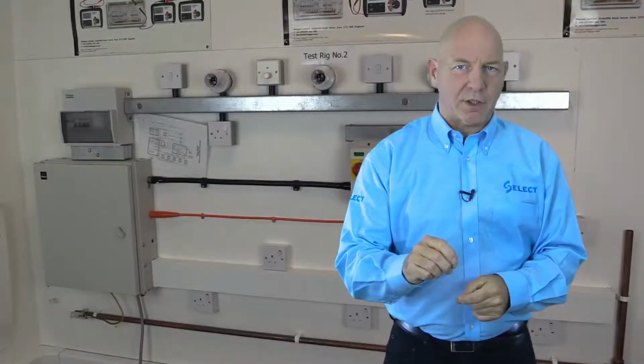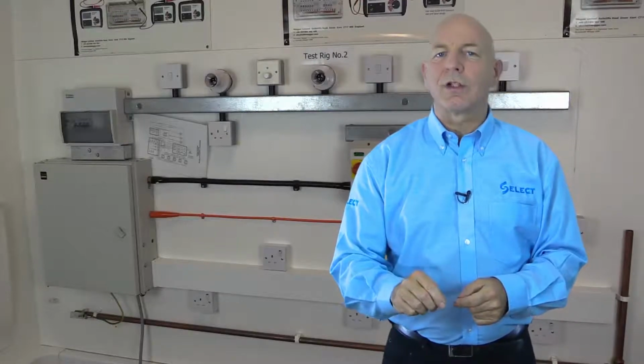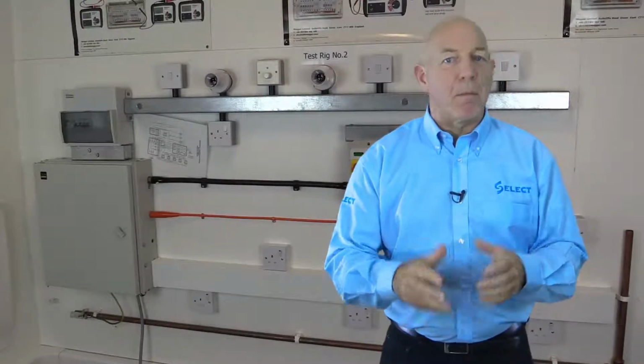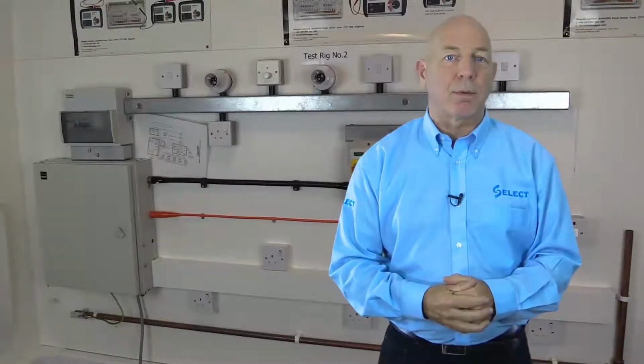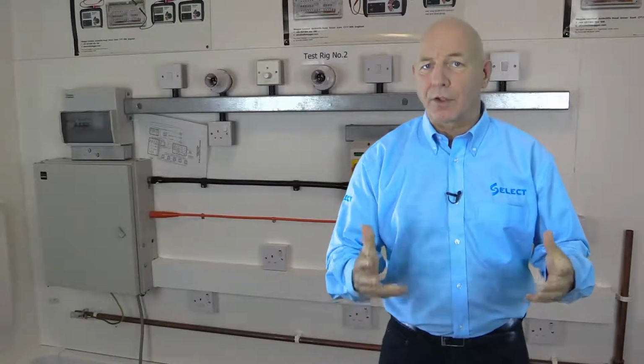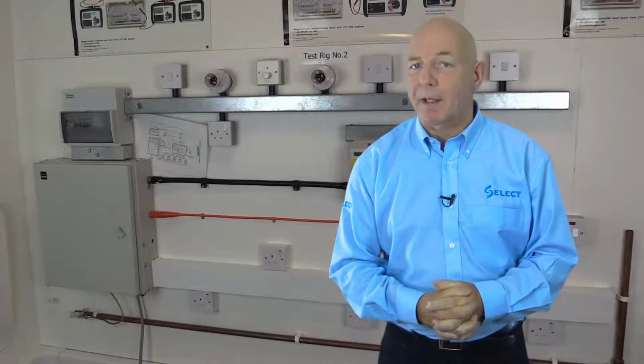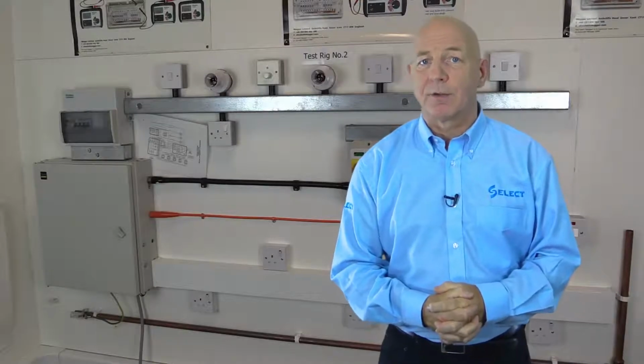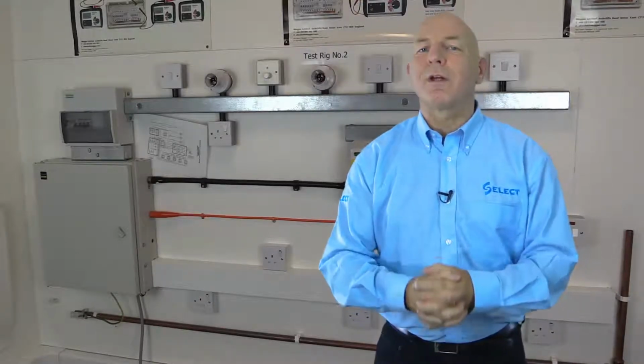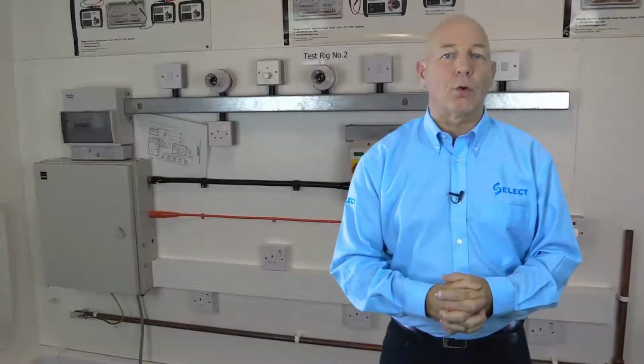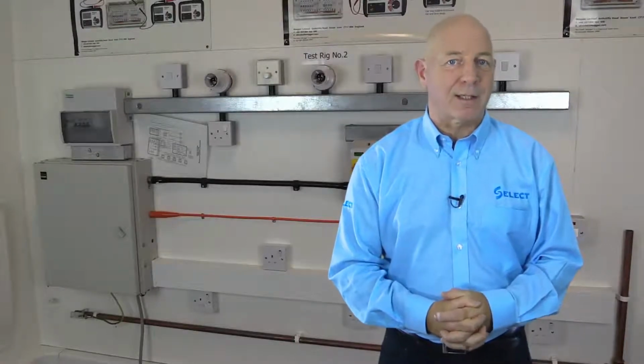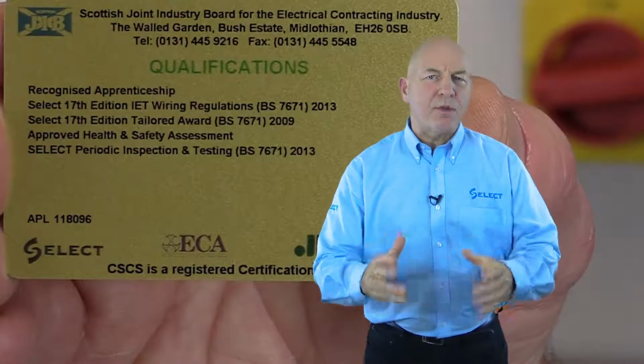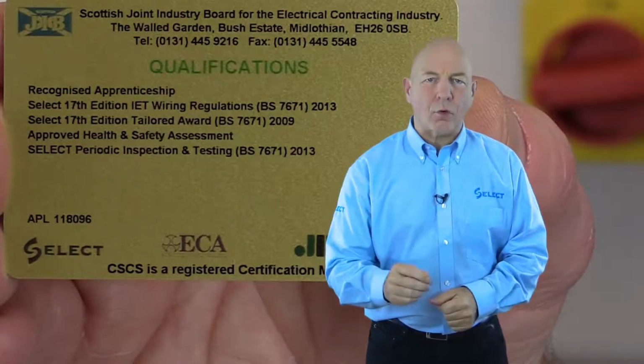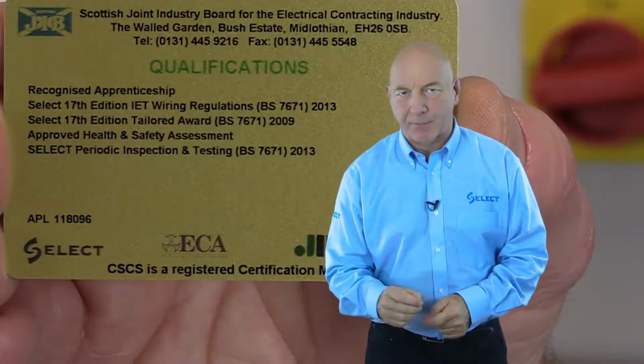Now, this regulation also requires that we consider safety precautions that may be necessary to avoid danger to persons and livestock. For example, other construction site operatives and the inspector carrying out the actual inspection and test, and to avoid damage to property and installed equipment during inspection and testing. Now, when it comes to safety precautions, we first of all should consider competency.